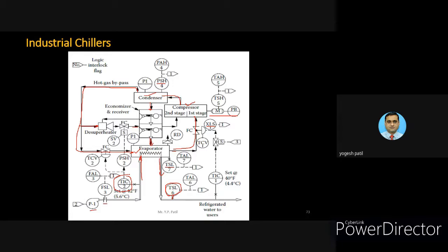TIC2 is what? Temperature indicator and controller. So this temperature indicator and controller is connected to the return water, right? Return water side. This particular one is the return water side. So this temperature indicator and controller is also used to control this particular valve connected over here, a solenoid valve.